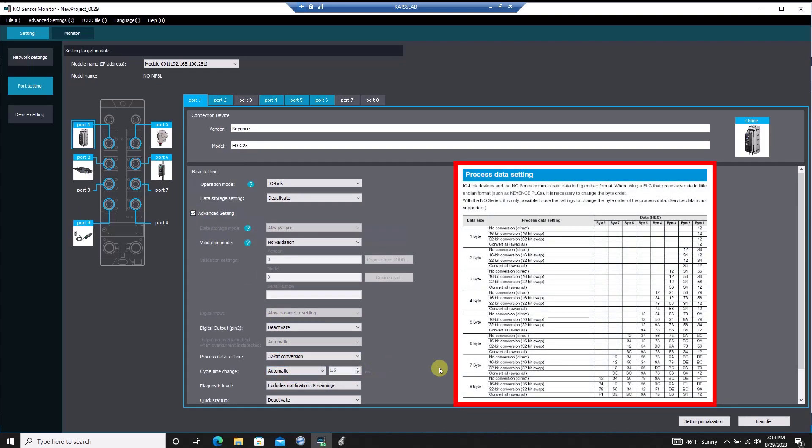The full list of parameters available can be found in the IO-Link instruction manual for that sensor. For example, I've got the FDG parameters pulled up now, and we can see that I need to use index 104 to reset the integrated flow. For Keyence sensors, which do not have sub-indices, I will always leave the sub-index field as 0. The swap mode field will always be 1 unless you're using a parameter with a byte length larger than 2, as this setting accounts for a difference in endianness between the NQ and the PLC. After all the AOI fields are filled out, we need to click on the bottom ellipses to set up the AOI itself. For writing a message, the service code will always be 4C and the class will always be 85. The instance and attribute should be filled out with a 1. For our source and destination elements, we want to select the tag that we created for the write data field in the AOI earlier. Lastly, we need to enter the communication tab and set up the path to the NQ, then click apply and exit out.